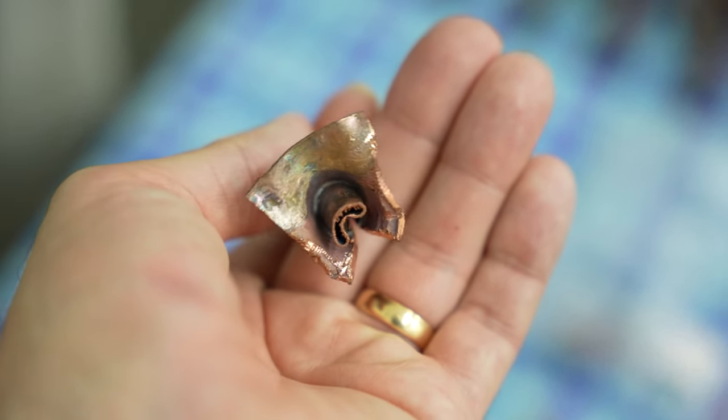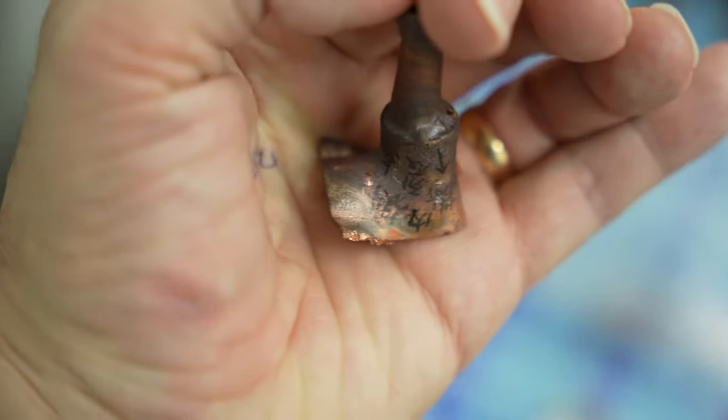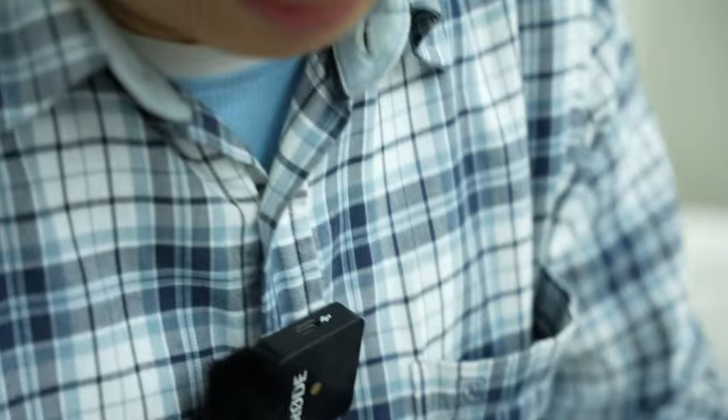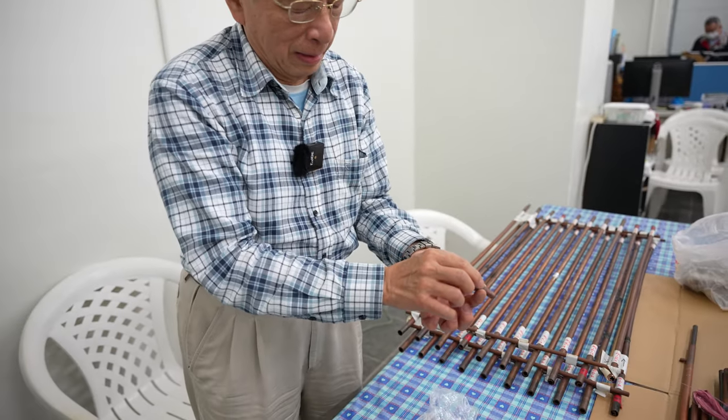And the crack is about 45 degrees — that means it's caused by stress, not a defect in the material. We'll have a look at that in a minute. It's been running for quite a long time, then got this one.